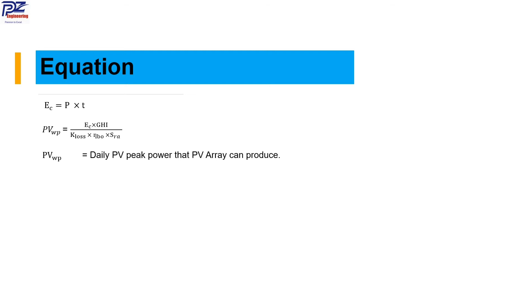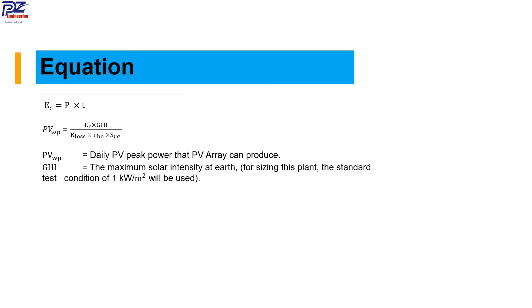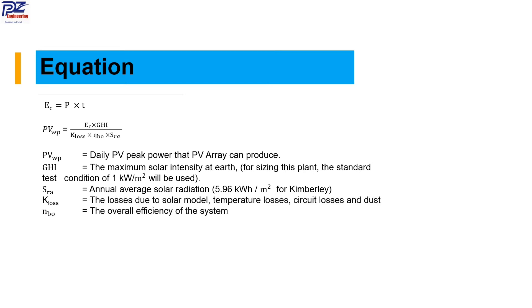Now we can go to our equations. Energy consumption is equal to power times time. For PV array sizing, we use energy consumption, solar irradiation, and losses. The PV peak is the daily peak the array can produce. We use maximum solar intensity of 1 kilowatt per meter square under standard conditions, with an annual average solar radiation of 5.9 hours — which depends on the area — and system losses.